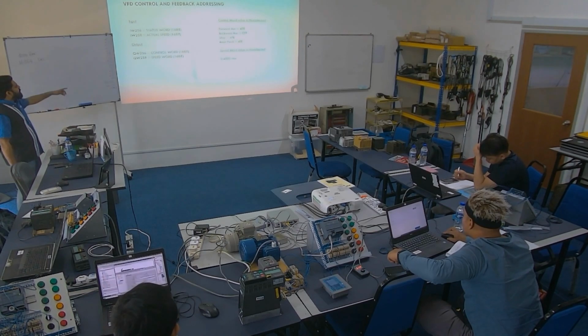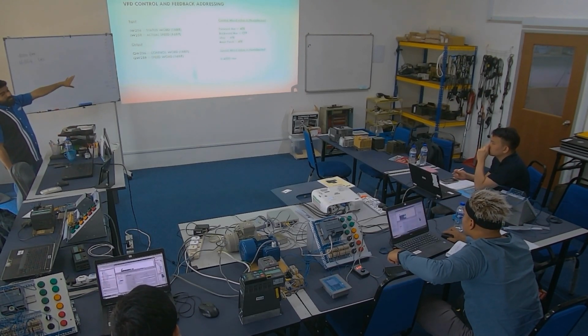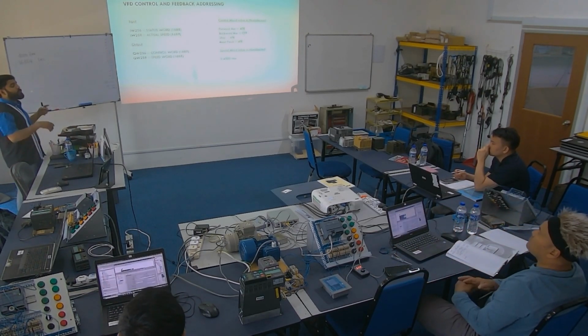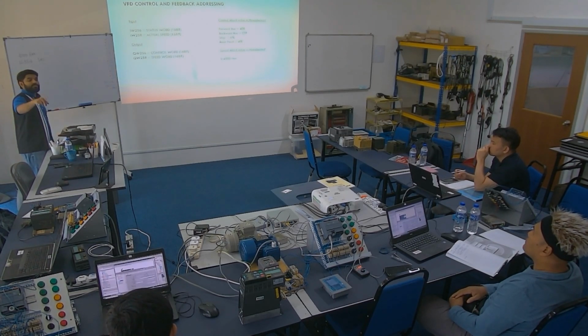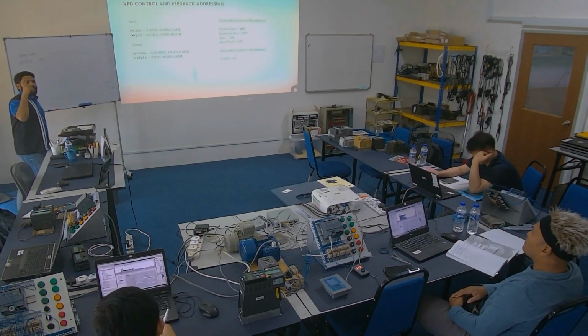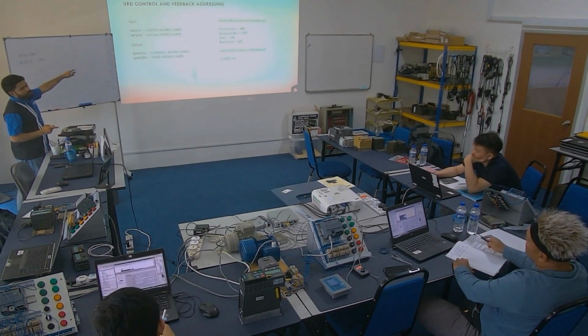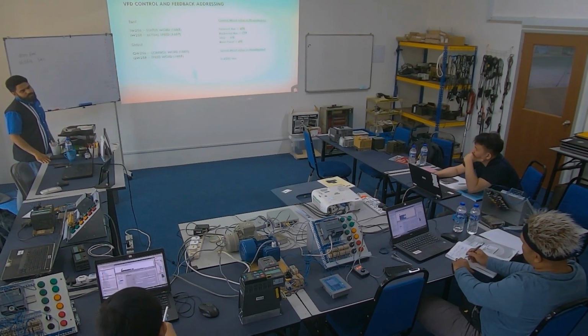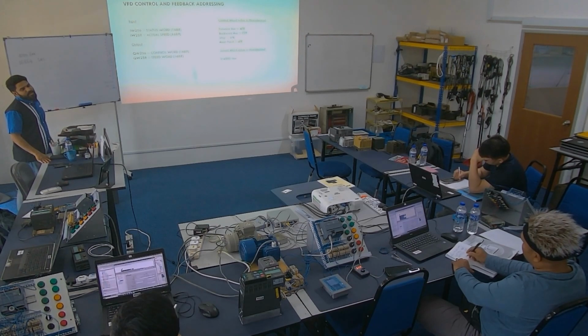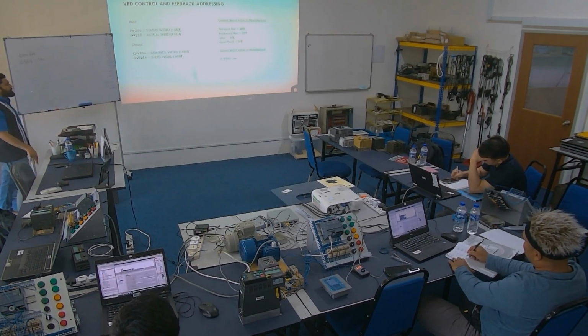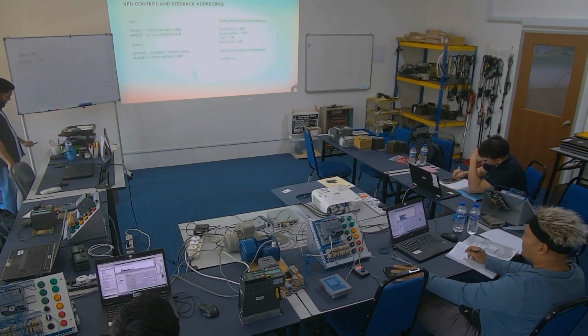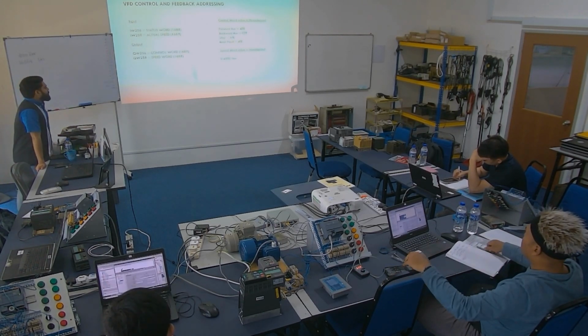So these are the data we need, taken from the manual of the drive. We choose Telegram 1, which has 2 inputs and 2 outputs. If you want more data, you can select more, like Telegram 2, Telegram 3, and so on.